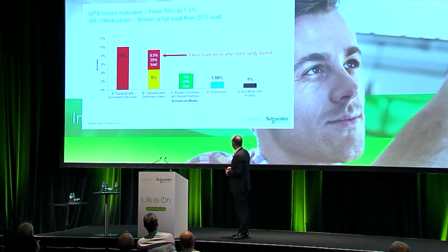So when you're starting to talk about efficiencies like this, it kind of kills the argument that a DC-based data center is going to be more efficient and all that kind of thing, because you're running with such massive efficiencies in your AC-based system. If we look at the 3-level when lightly loaded, most of them would go up to about 9.5% losses down at that 25% load. And you can see that in the 4-level, again, it's only a very minor change there. So quite a significant jump in that area.